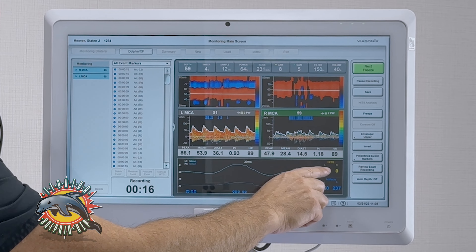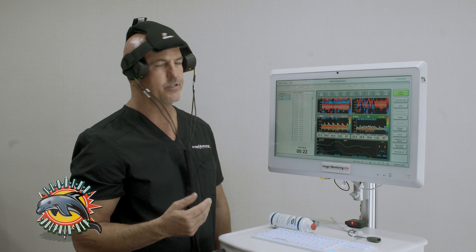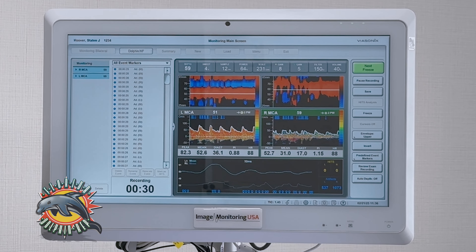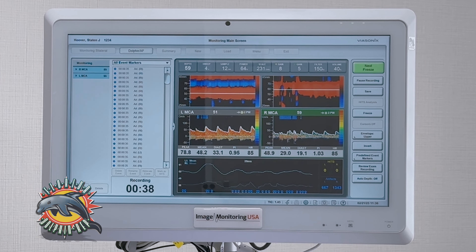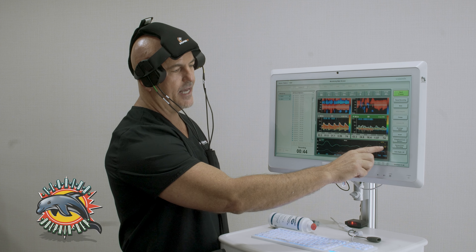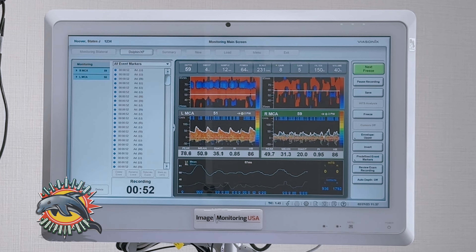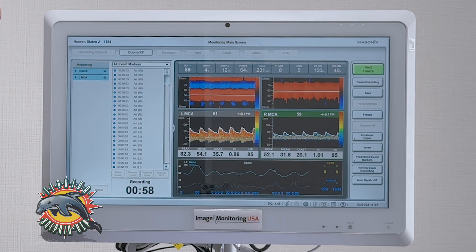Now I'm going to start recording and Dolphin XF. The monitoring session has begun. The software has a hits counter because we're going to be monitoring for microemboli. This is used for pre-, during-, or post-operative monitoring, and it's also great for stroke patients to make sure there are no more emboli entering the brain that could cause a stroke. Obviously I'm healthy and that's why the hits counter shows zero, but every time I talk it's creating artifacts because the software is also counting artifacts.